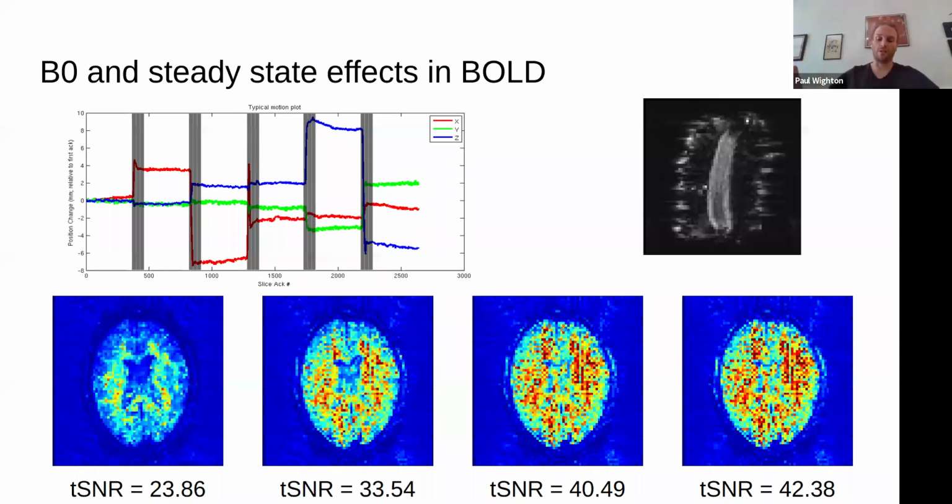One thing the EndoScout guys have is this giant cube that fits into where you would put a head coil, and the cube has a bunch of little square openings in it, like maybe 10 by 10, right? And then they have this long sensor stick that has maybe 10 sensors on it, and they put it into each hole, get measurements, put it into the next hole, get measurements, and that's how they do their calibrations. So they know that when the sensor stick is put into this cube, it's exactly 10 millimeters or whatever it is away from the adjacent one. Okay, that makes a lot of sense.